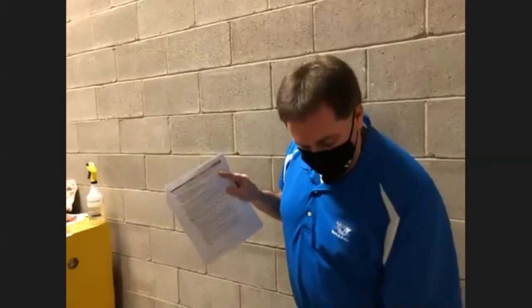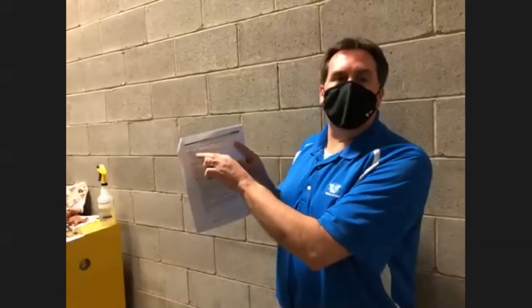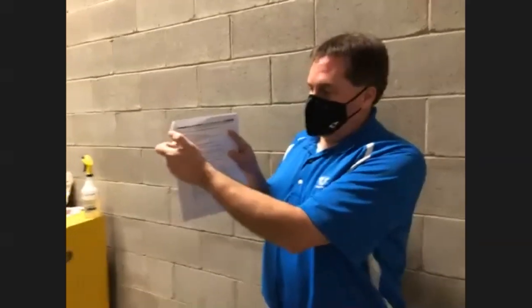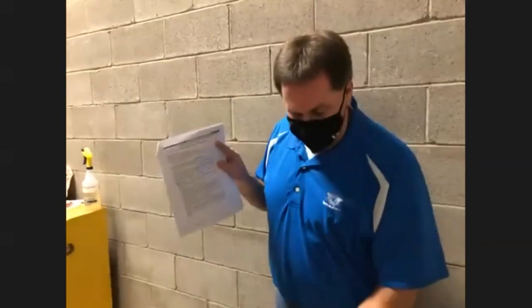This is a 24 volt system. After you plug it in, it's normally 120 or 230 going in. Once they run through transformers, they're a 24 volt system. So many things you will need to check are 24 volts between many connections. So truly go step by step. Go through this and you will find the issue if you were not successful at finding the issue by doing general inspections.